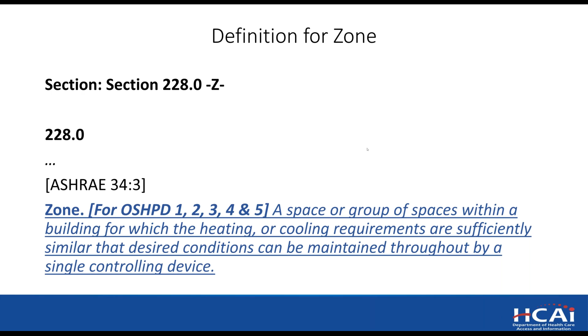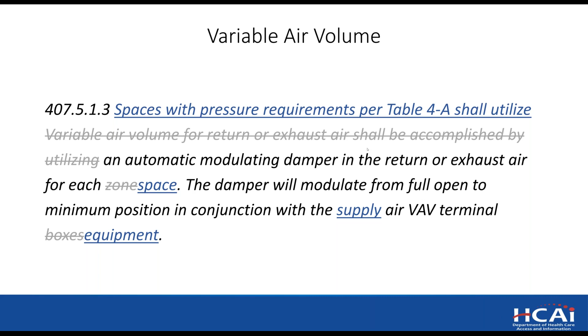Next slide, please. The next change had some rearrangement and revision to 407.5.1.3 of the California Mechanical Code for variable air volume. OSHPD proposes to amend the variable air volume section to specify that a VAV device is required in spaces with pressure requirements. This is to ensure spaces in Table 4A will be provided with necessary equipment to maintain pressure requirements. In these systems, a supply box may be provided with constant volume, but the return airflow can fluctuate. This change helps keep supply and return differentials throughout the range of operation, as required in CMC 407.5.1.1.